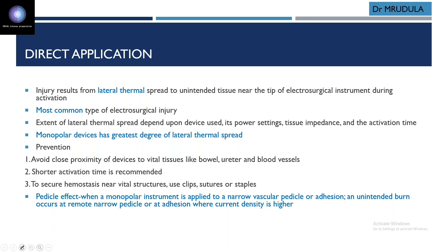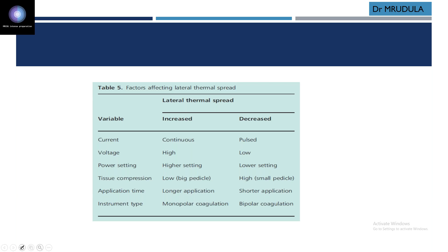So factors which affect this lateral thermal spread are current: continuous current increases the lateral thermal spread, while pulse current decreases it. High voltage, a higher setting, increases lateral thermal spread. Low tissue compression: with a big pedicle, you cannot achieve proper tissue compression, so it will also increase the lateral spread. Application time: longer application is associated with more lateral thermal spread, and monopolar is associated with the highest lateral thermal spread.